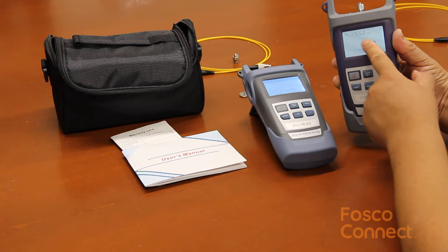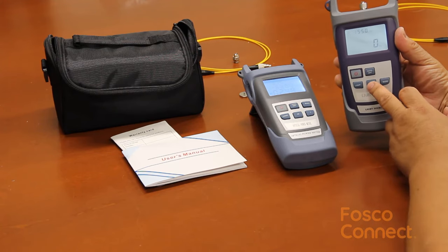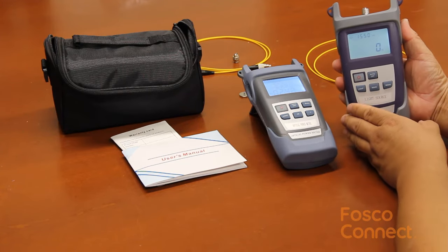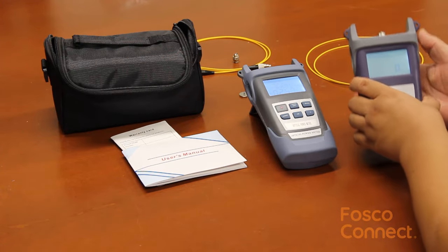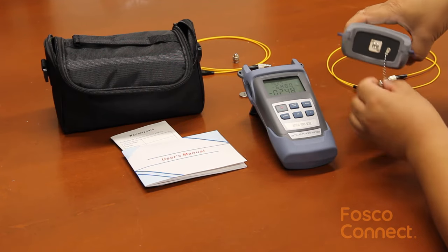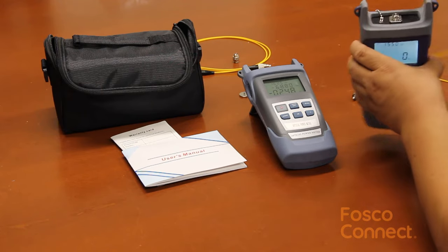It has two lasers built in, 1550 nanometer and 1310 nanometer. We are going to use the 1550 nanometer light source. The light source has an FC adapter interface. Let's plug in an FC single mode patch cable.